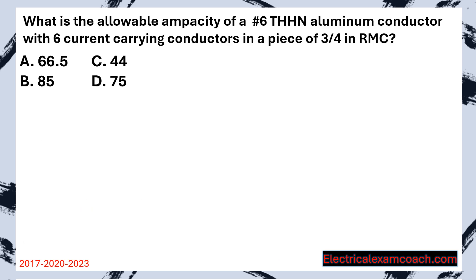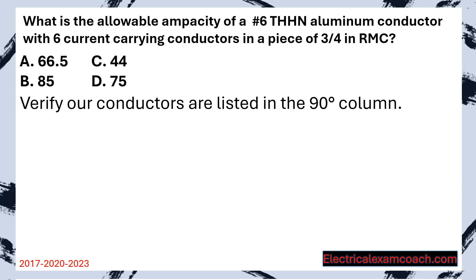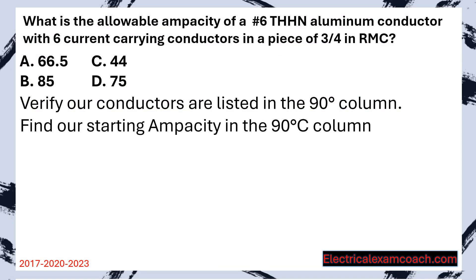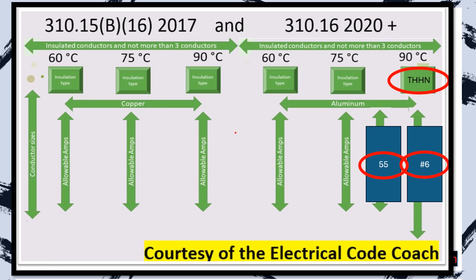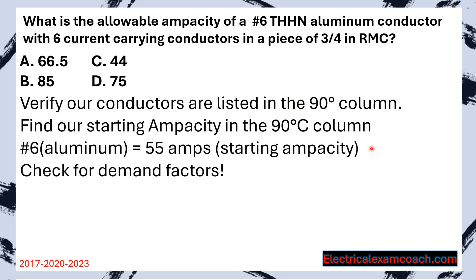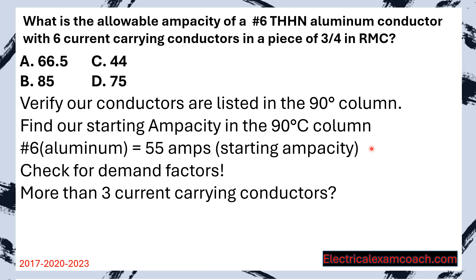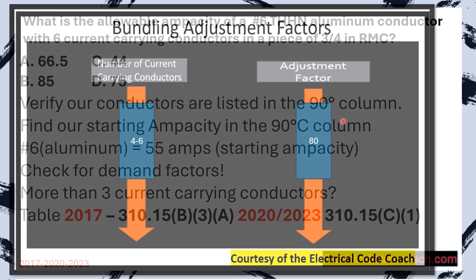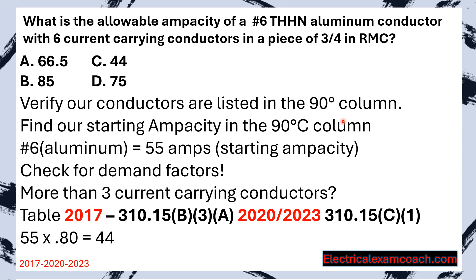Practice question: What is the allowable ampacity of a number 6 THHN aluminum conductor with six current carrying conductors in a piece of three-quarter-inch RMC? Step one: verify THHN is listed in the 90°C column on the aluminum side — it is. Step two: on the aluminum primary ampacity table, find number 6 and cross to the 90°C column — starting ampacity is 55 amps. Step three: more than three current carrying conductors, so head to the bundling adjustment factor table. Taking 55 amps multiplied by 0.80 gives a new reduced allowable ampacity of 44 amps.